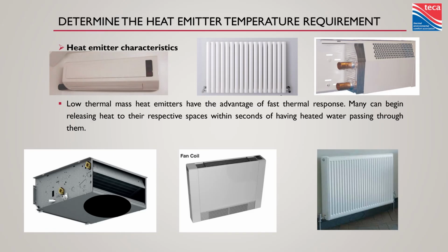This would be my advice. Go with a fan coil for chilled water cooling. Now that fan coil could also be used for some heating. So maybe the top floor of the house is a fan coil, bottom is radiant floor, or maybe you have one heat emitter that does one thing and the other is strictly cooling. That's okay too. Lots of ways to control these things and pipe these things.